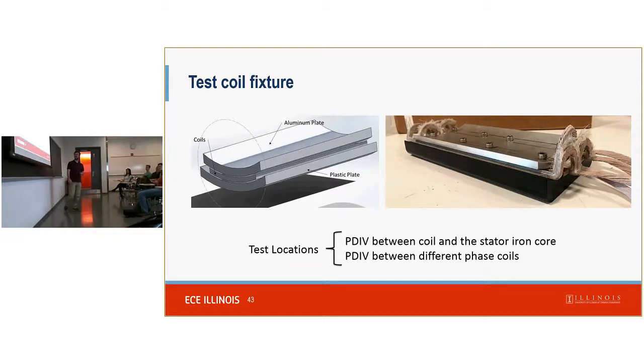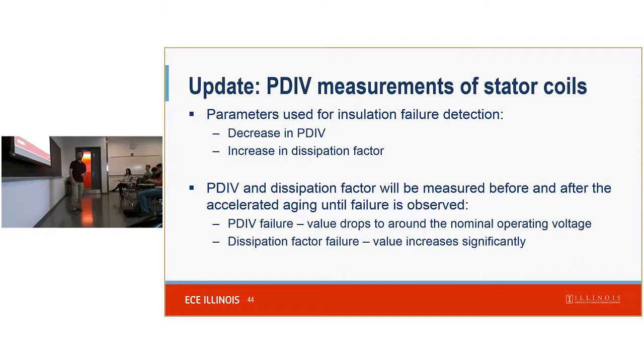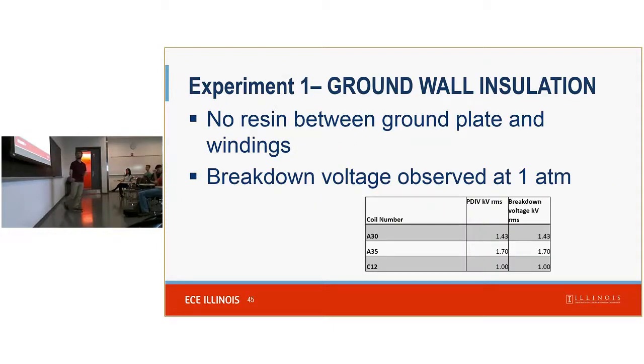So this is showing a test coil fixture. The way this works is that this metal plate is connected to ground and high voltages are applied to these coils, either from a coil to the plate or between two coils. That allows us to test the insulation on different sides of those coils, say the side facing ground or the side facing another coil. And so the goal here is to measure the partial discharge inception voltage before and after this accelerated aging process.